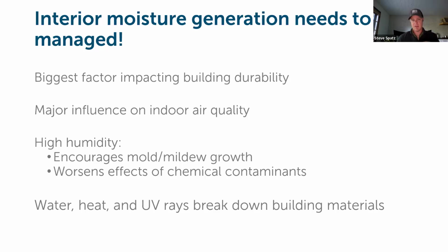So there's a sweet spot of relative humidity to maintain during the heating season. And during the heating season is where we're getting moisture and vapor drive into our building assemblies. So we can do the best we can, and we should be doing the best we can, with keeping moisture out of assemblies and air out of assemblies, but we do have to keep relative humidity in check inside the building with some mechanical system that is going to keep moisture in check, and then also eliminate pollutants from the building and just create a good, healthy indoor air quality environment.